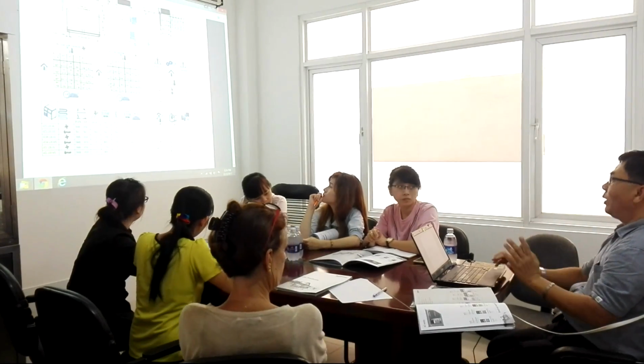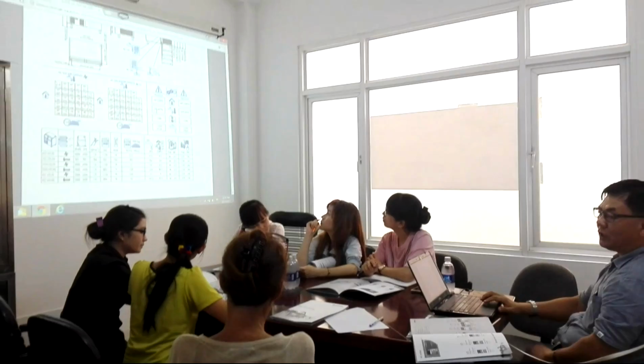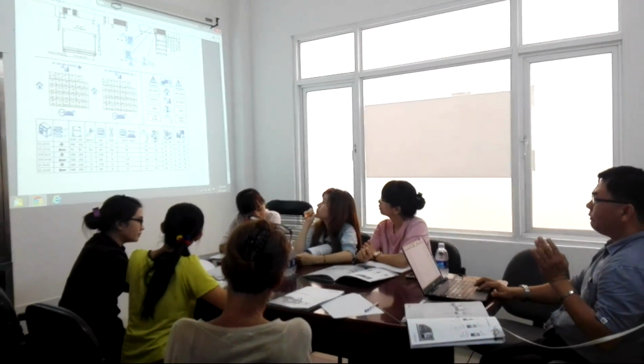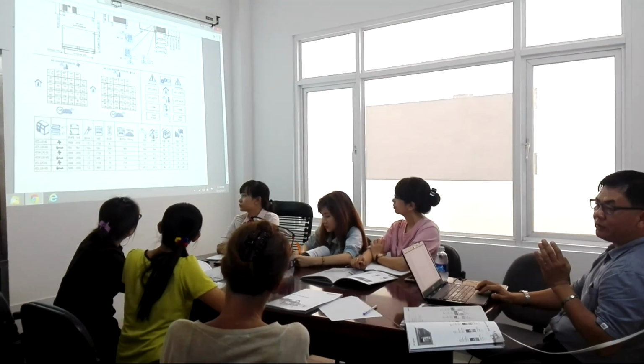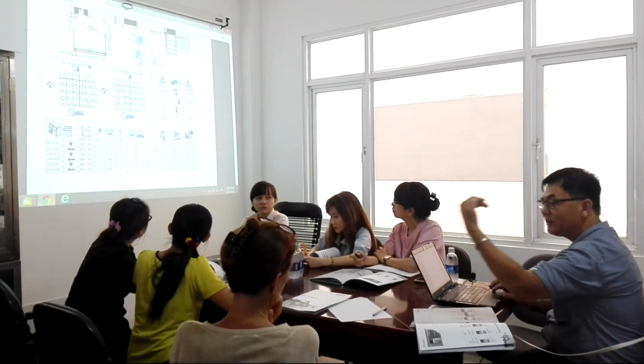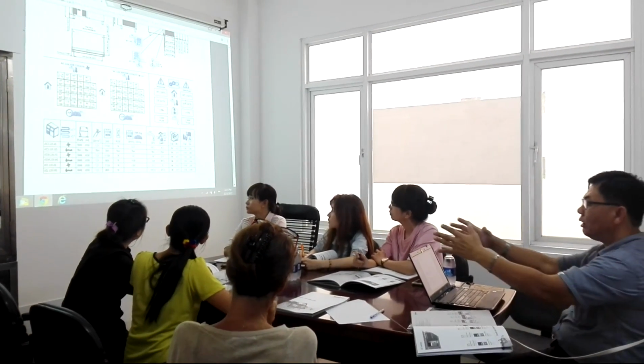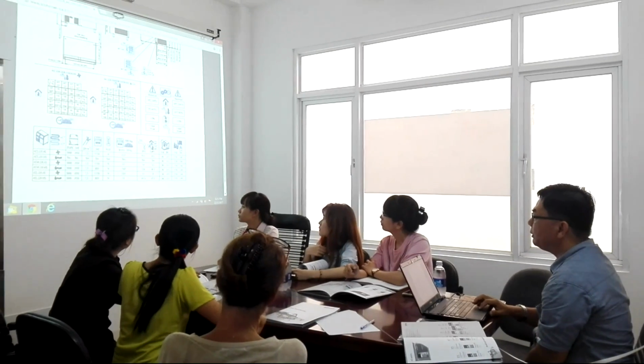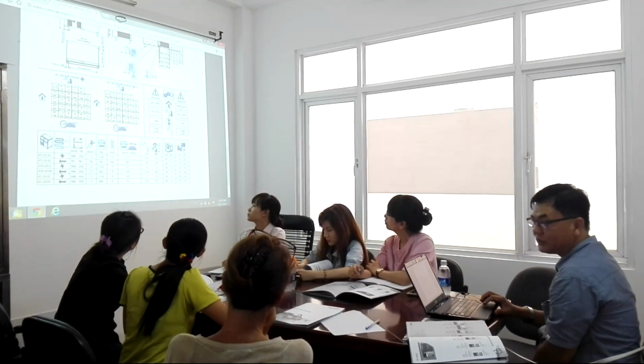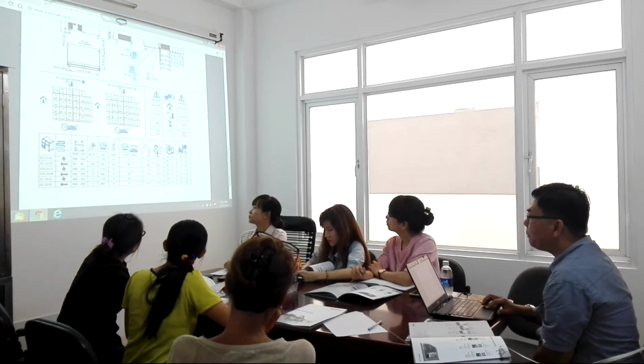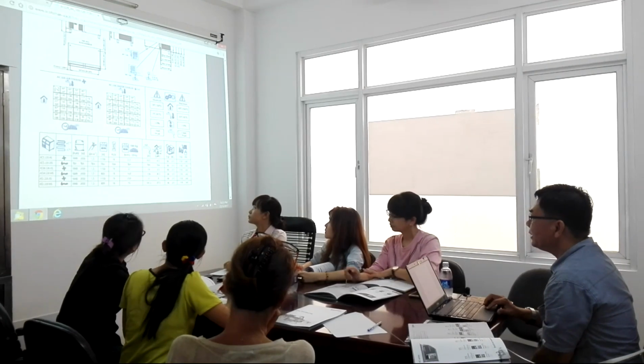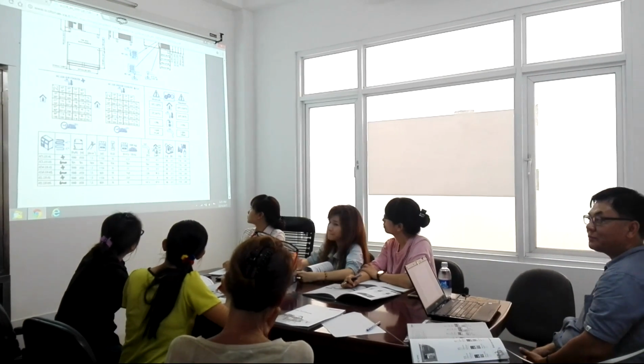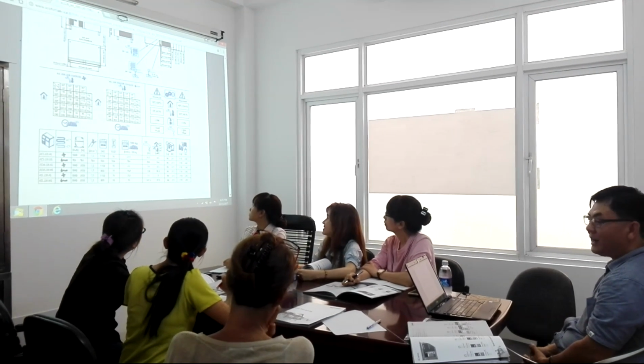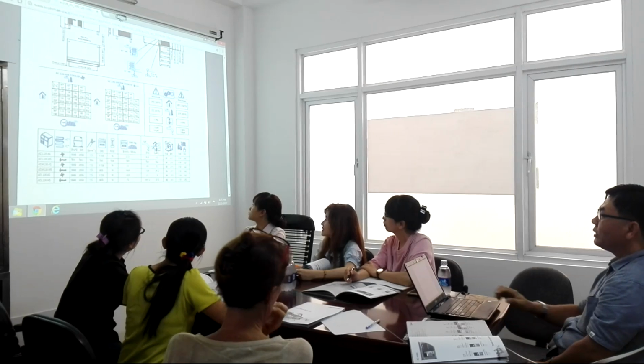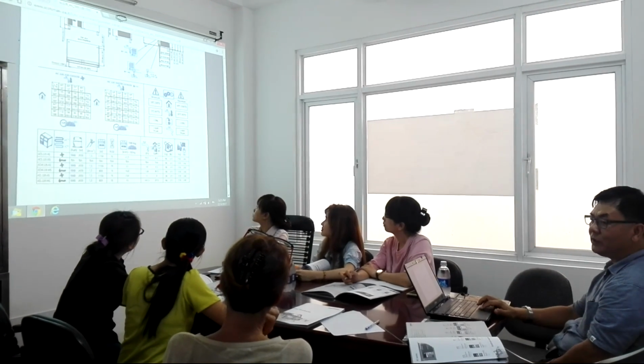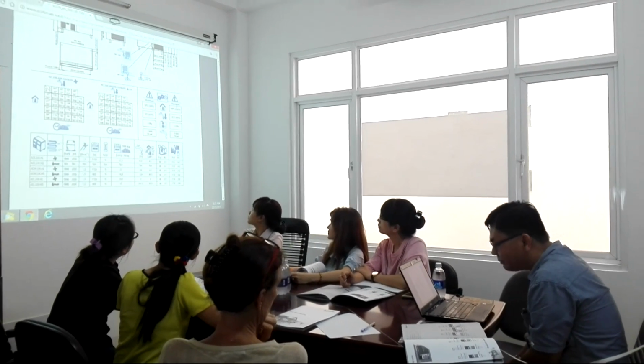So now we talk about water. The water temperature for my machine should be between 5 degrees and 35 degrees, meaning the temperature of the incoming water. The temperature of the air going into the machine must be between 10 degrees and 40 degrees, and the water pressure must be between 1 bar and 5 bar. This is my design criteria. If the air temperature goes higher than 40 degrees, the machine can stop to protect itself.